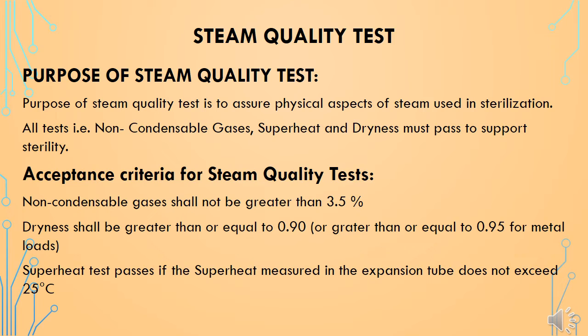The next qualification test is the steam quality test, performed to ensure the quality of steam provided to the sterilizer meets acceptance criteria. In this test we check non-condensable gases, superheat, and dryness of the steam. Acceptance criteria: non-condensable gases shall not be more than 3.5%, dryness shall be greater than or equal to 0.90 (or ≥ 0.95 for metal loads), and the superheat test passes if the superheat measured in the expansion tube does not exceed 25 degrees Celsius.